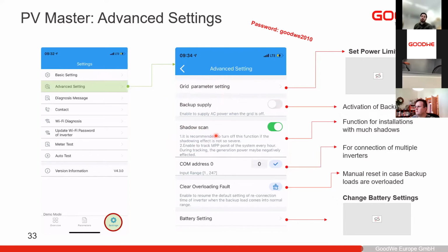This function is called shadow scan. It is for when your PV modules have frequent shadows, usually not from clouds, but from a chimney or big trees nearby that cover the modules frequently. Then you can have this activated for the MPPT to scan much more frequently. By default it will scan once every hour. In case you do not have any shadows on your PV system, we recommend that you do not activate this, because when it scans, it takes some time, and during that time the inverter does not generate any output. So to optimize the yield, if you do not have shadows on your PV plant, leave this out. Only if you have shadows will it be beneficial for your generation.